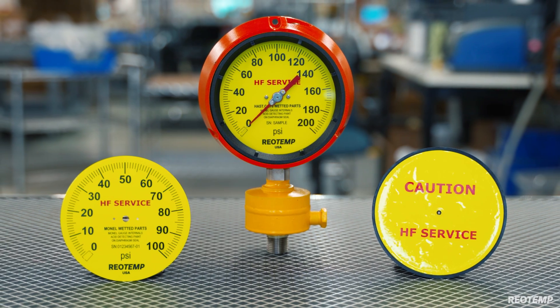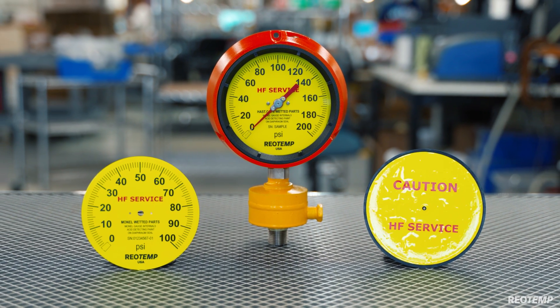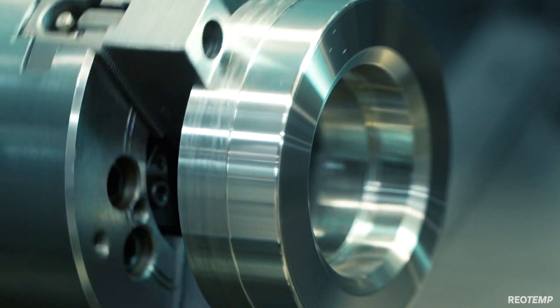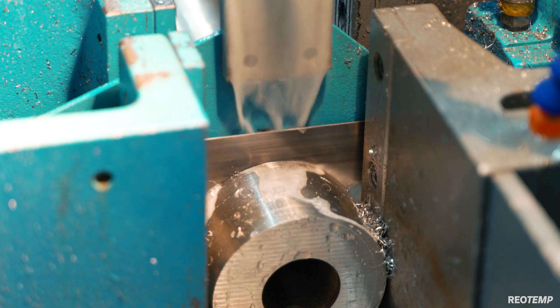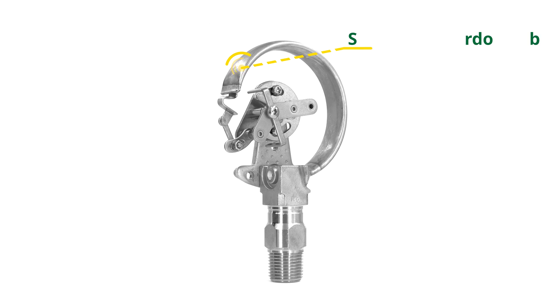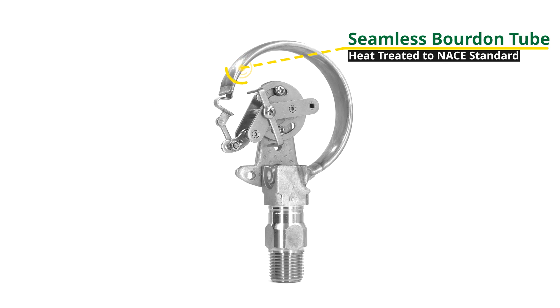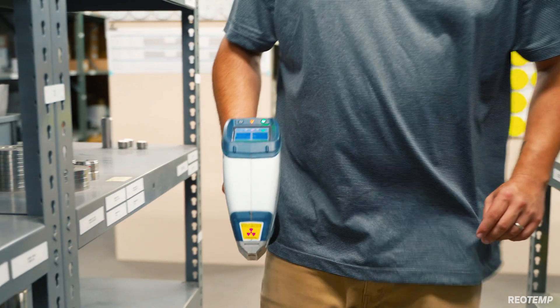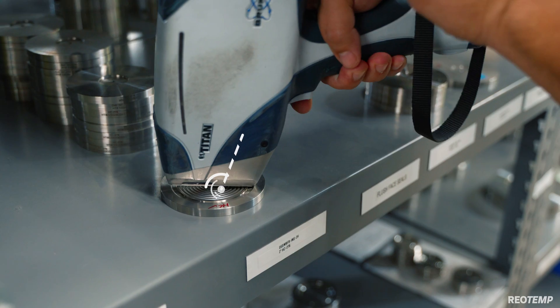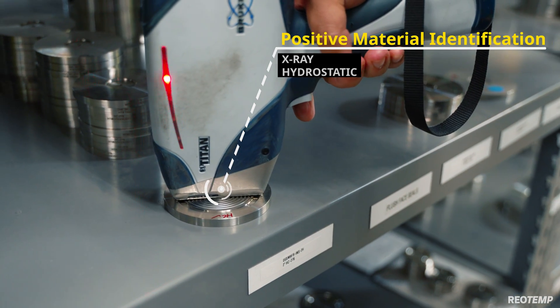The gauge comes standard with a service alert on the dial front and rear. The high-vis dial is standard, and orange or yellow cases are options to increase visibility and operator awareness. All machine components are fabricated from certified rolled bar stock — we never use castings. We only use seamless tubing on Bourdon tubes and heat treat them to NACE standards. We offer positive material identification, x-ray, hydrostatic, and other non-destructive testing options.